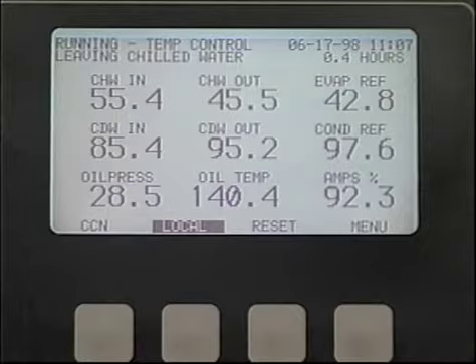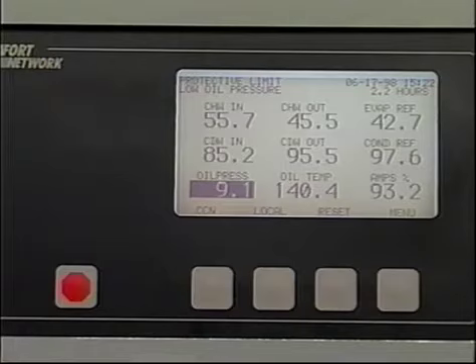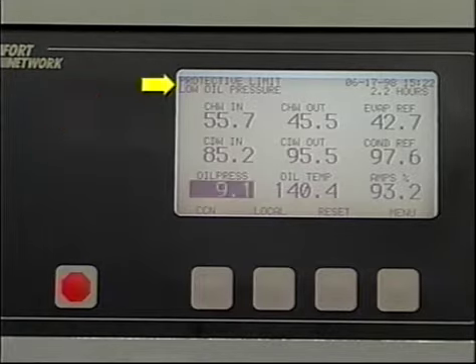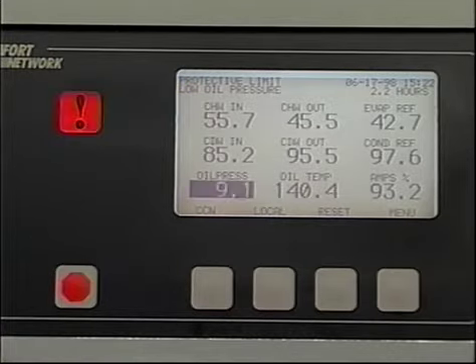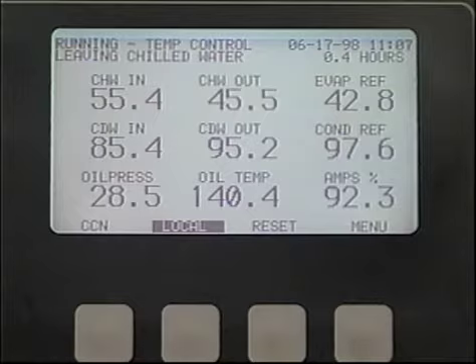You will quickly learn the normal values of these points, and will be able to confirm that operating conditions are normal just by checking the lid screen periodically. And if the chiller is not holding the load conditions, or is shut down when it should be running, the lid screen will help identify what's wrong. If an alarm has occurred, the lid screen will display a message identifying the cause of the shutdown. The lid can be used to access considerable other operating data as well.